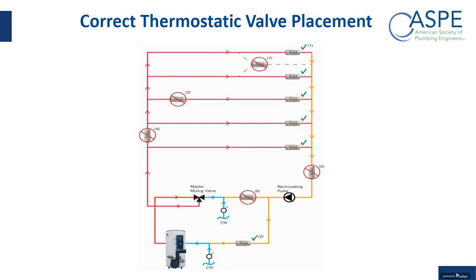And lastly, there's another application for a thermostatic balancing valve, and that is if you have a mechanical master mixing valve, and sometimes you're fighting with how much flow do I want back to the master mixing valve and how much do I want back to the water heater, because I don't want to have too much flow back to the water heater where I have temperature creep during the night when nobody's using it, and I have a master mixing valve which always has some flow going through it. Overnight the temperature could start creeping if you have too much flow back to the water heater. If you don't have enough flow back to the water heater, you basically will have temperature droop.